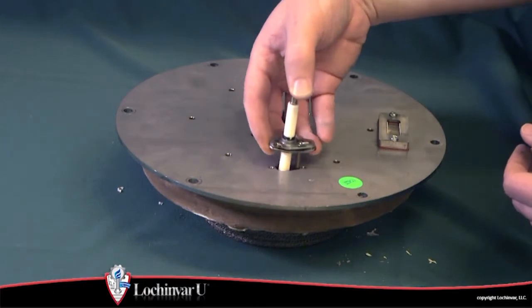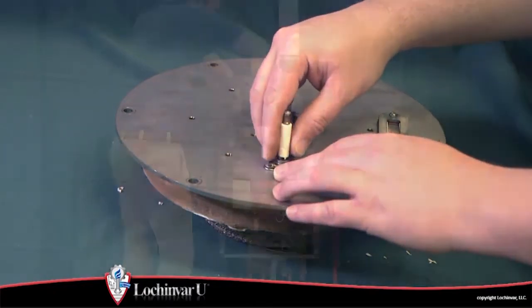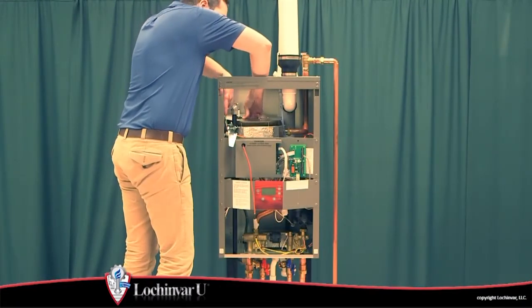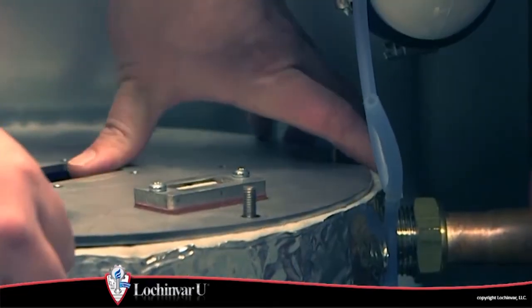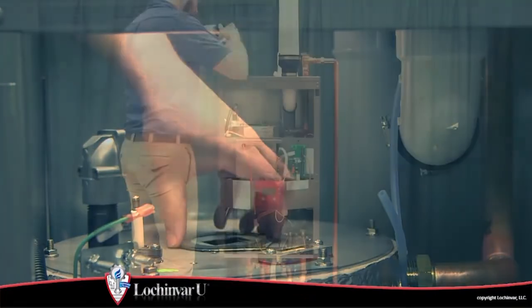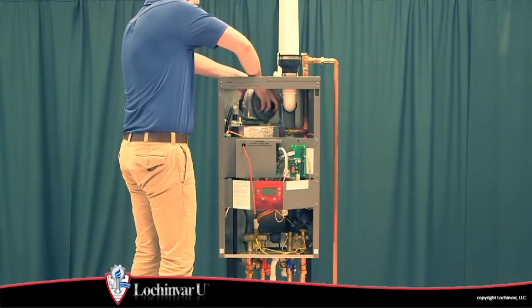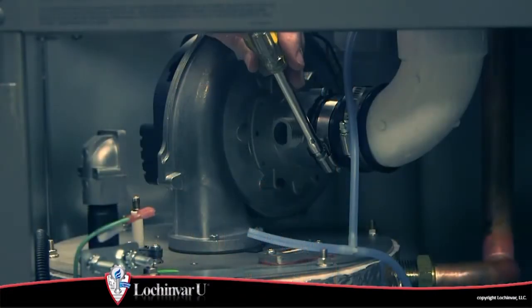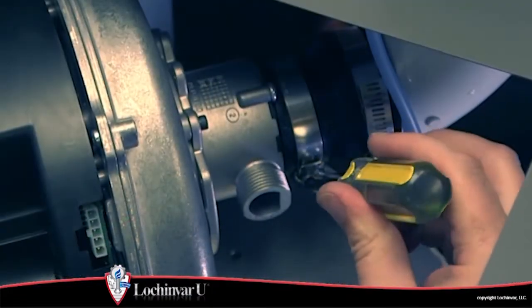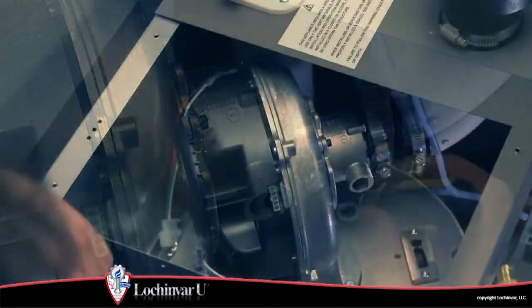Then reattach the igniter to the heat exchanger top plate and replace the heat exchanger top plate and secure it to the heat exchanger. If equipped, replace the air shutter and then replace the fan assembly to the heat exchanger top plate. Reconnect the air intake piping to the fan assembly. Then reinstall the gas valve.